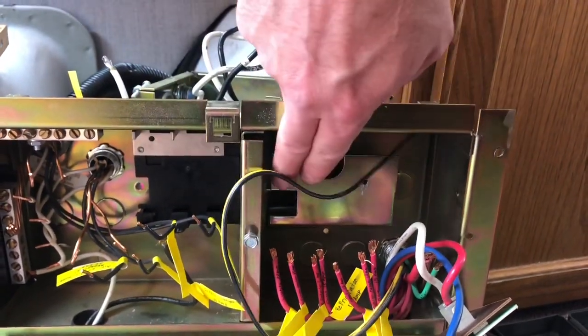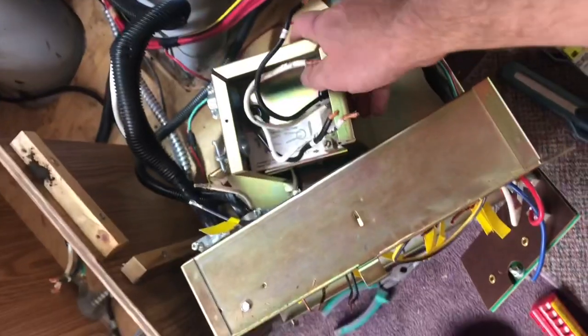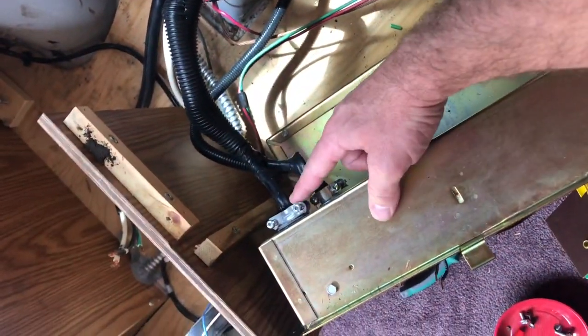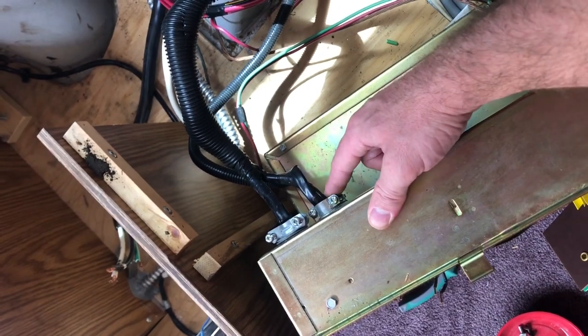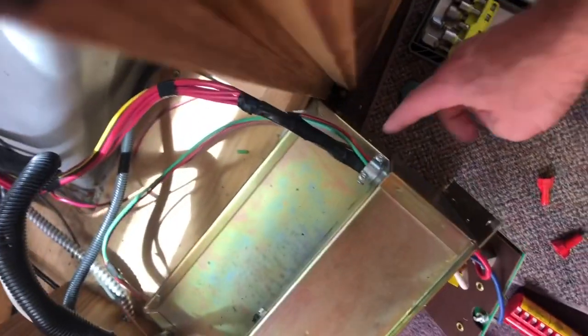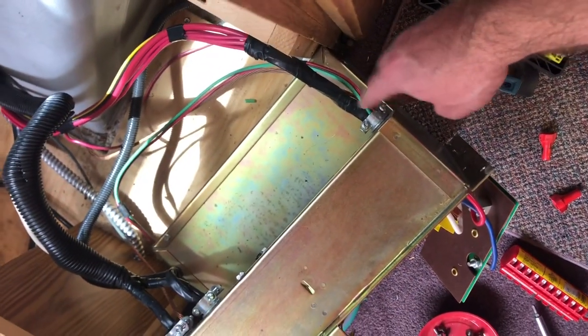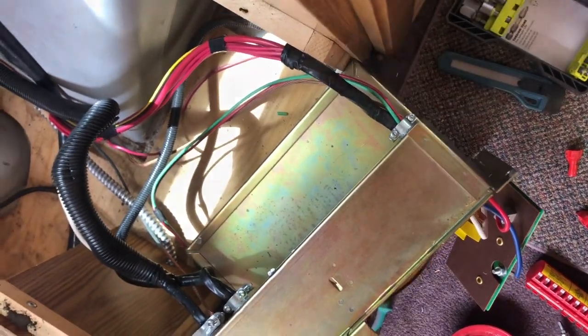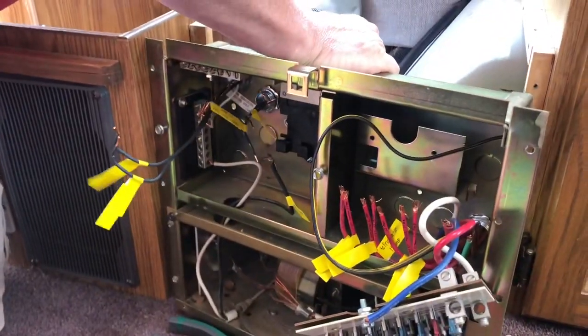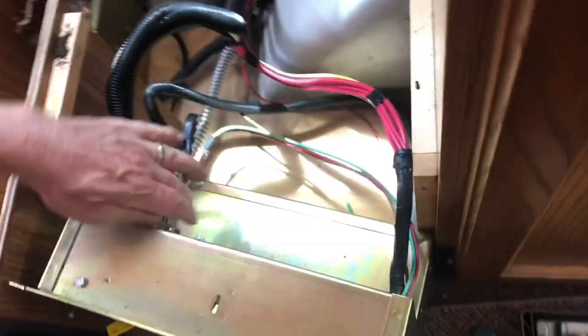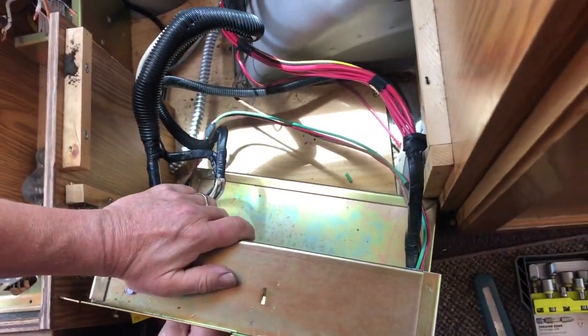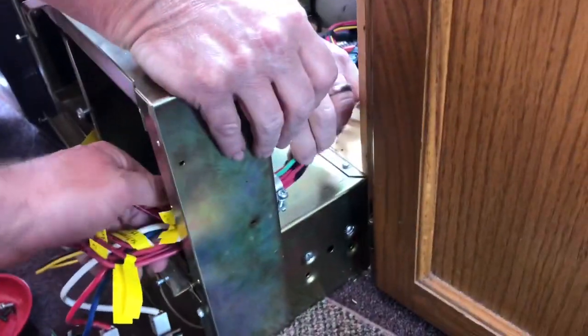So pulled the automatic transfer switch again. You got the one screw there, you got the other one right there, and then the whole automatic transfer switch comes off. So now all we have to do is pull the two AC lines here, and then we'll come down and get the square nuts off and pull off the DC side. Those AC ones, you just kind of got to straighten them out and you can yank those out on the back side.